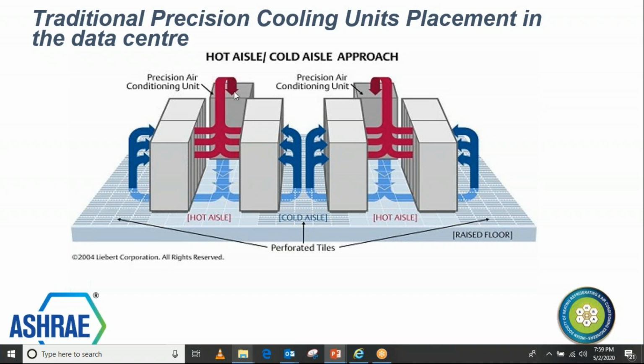Here you can see the supply grills. These cooling units are pumping cold air under the floor, so this acts like a plenum, like you have in a ducted system, which most of you are very familiar with. You can say this is virtually a plenum here, and you have supply grills where cold air comes out and goes inside the racks, exchanges heat and goes back to the cooling units. Why are these cooling units positioned in the hot aisles' front? Because this is the lowest path for the hot air to go back, it reduces the loss on the fan, and at the same time it avoids hot spots in the room. So this gives a good circulation of hot and cold air supply. This is very important to understand. Where the cold air comes out is known as the cold aisle, and where the hot air goes out from the servers is called the hot aisle.